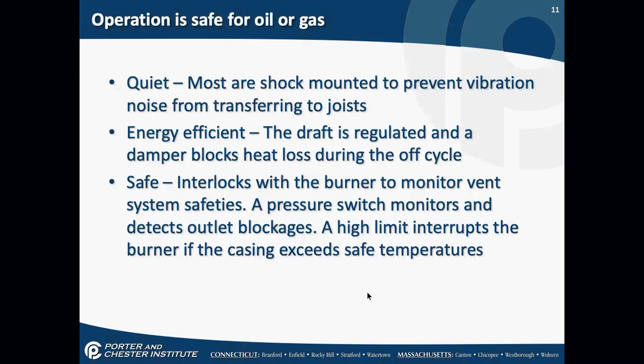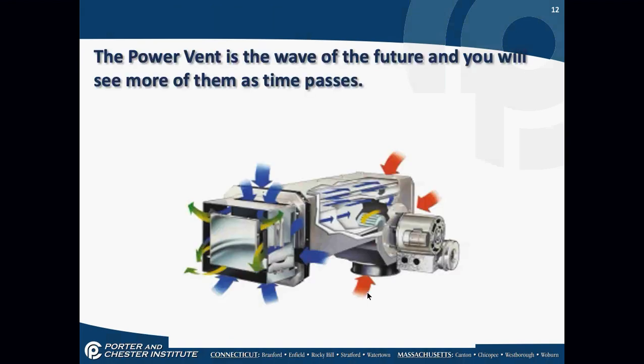In other words, if the snow gets too high on the outside of the building, the thing is going to shut down and shut the furnace down. A high limit switch interrupts the burner if this gets too hot. Okay, so there's a lot of safeties in this thing to prevent overheating, no output, and the motor not running. Okay, a lot of safeties in here, but this all becomes part of your ignition sequence. Thermostat calls for heat. The power venter has to start first. The power venter has to be proven that it has started before we can start the furnace or the burner. Okay, first step of the process. Power venter doesn't start, nothing's going to run.